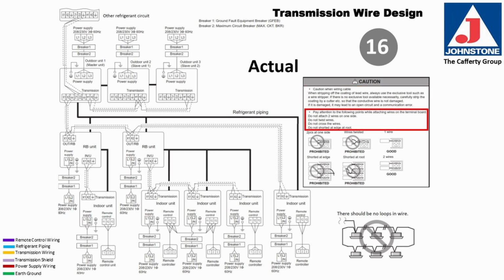Pay attention to the following points when you're attaching the wire to the terminal board. Do not attach 2 wires to one side of the terminal. Do not twist the wires together. Do not cross the wires. Make sure the wires can't short together, either entering or leaving the terminal block. And wire the system as highlighted here.